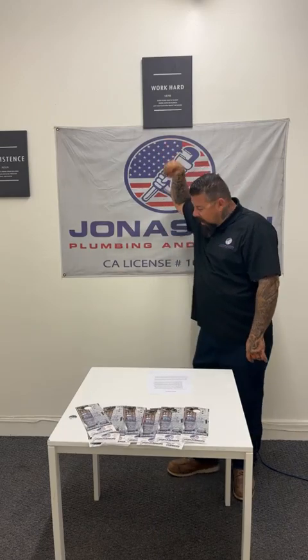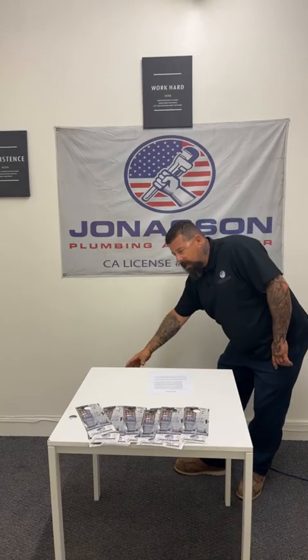Because what happens with the storage tank water heater is your cold water comes in from up top and your hot water goes out up top. The Bradford White water heaters we recommend installing have what's called a hydrojet system at the bottom. So instead of the cold water just kind of raining down in the tank, it has a pipe that goes all the way through, and then at the bottom it starts to swirl when the water's filling up into the tank. That helps with a lot of calcium deposits and rust deposits or any other sediment that comes in from the city water into your water heater.